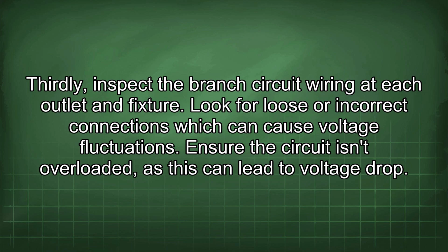Thirdly, inspect the branch circuit wiring at each outlet and fixture. Look for loose or incorrect connections which can cause voltage fluctuations. Ensure the circuit isn't overloaded, as this can lead to voltage drop.